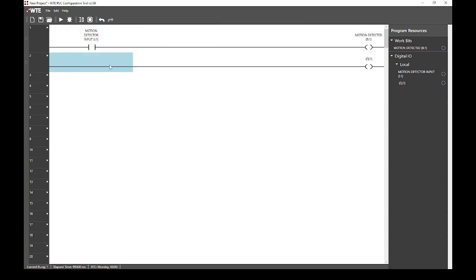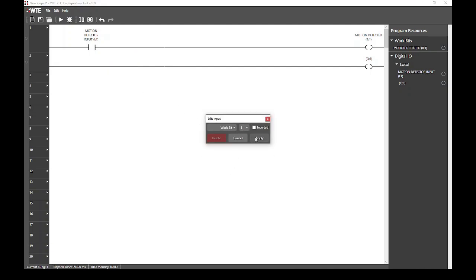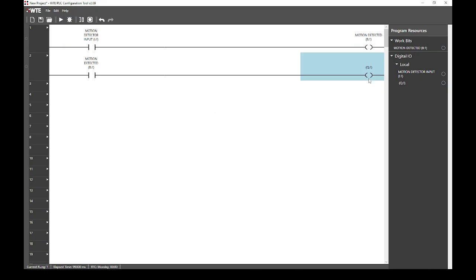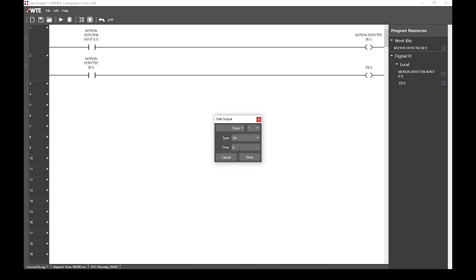We then set the work bit as the first rung input. Note that the name we configured appears here. Next, we need to set the output to enable timer 1. Now we can see that this dialog window has changed. We can now configure timer 1's parameters. We want to set this timer to trigger after 10 seconds. Note that the time configured here is in 100 millisecond steps. This means that we need to set this value to 100 to get a timer that will trigger after 10 seconds.